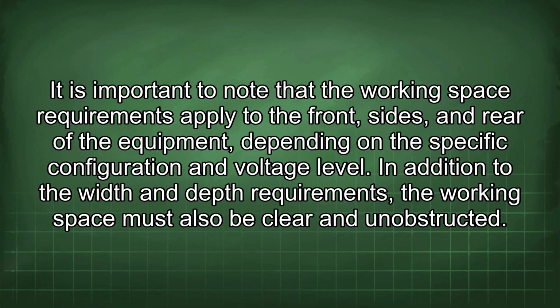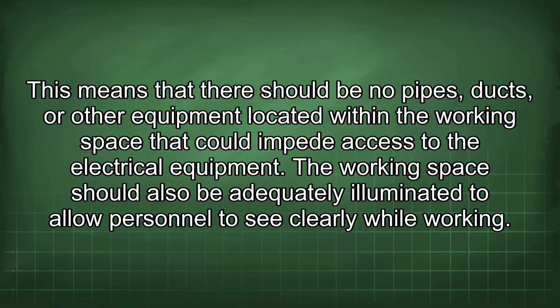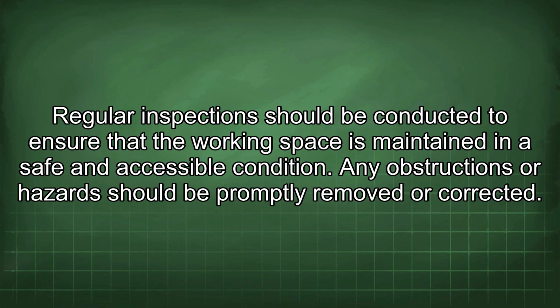In addition to the width and depth requirements, the working space must also be clear and unobstructed. This means that there should be no pipes, ducts, or other equipment located within the working space that could impede access to the electrical equipment. The working space should also be adequately illuminated to allow personnel to see clearly while working. Regular inspections should be conducted to ensure that the working space is maintained in a safe and accessible condition. Any obstructions or hazards should be promptly removed or corrected.